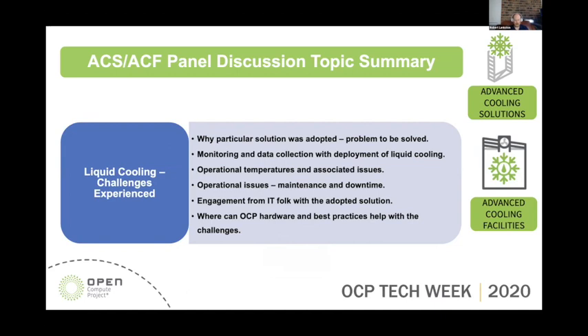When we get to server design, we talked about the interaction between elements that were once isolated on their own. A server in air cooling is often viewed as its own point in a rack, and a rack as its own point in a data center. A lot of those lines get much more blurred in liquid cooling systems. As Jessica mentioned, you have to take a more holistic view, from the facility down to the server level, to get everything integrated and communicating together. There are a lot of systems that need to be revisited in terms of management and monitoring, to get those systems communicating together.